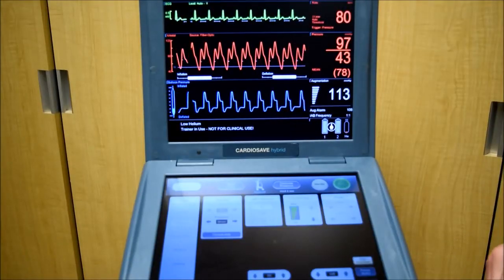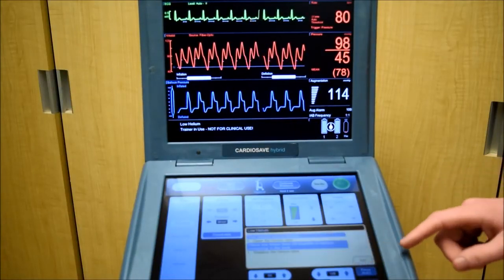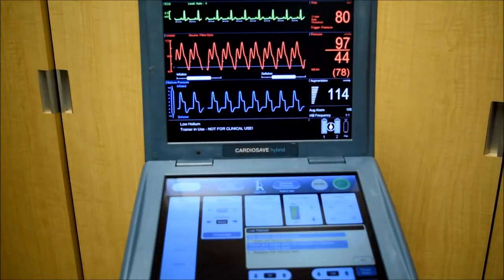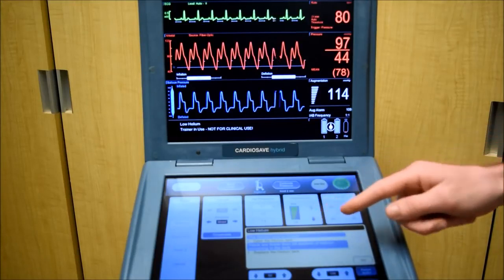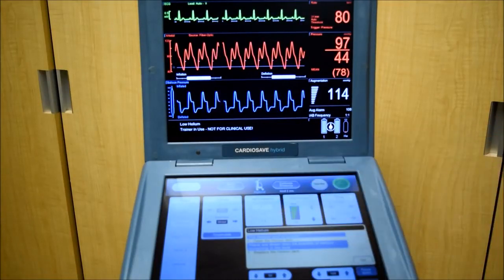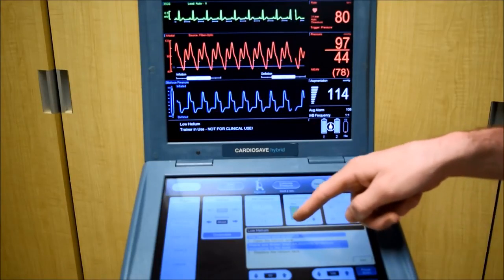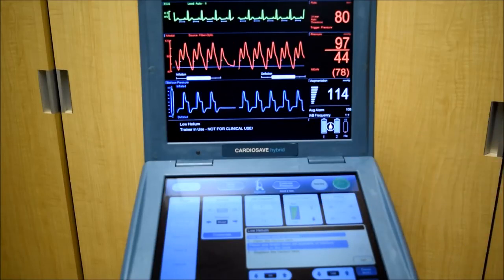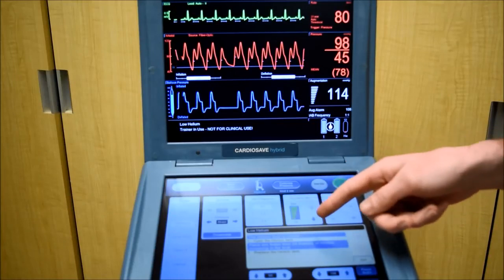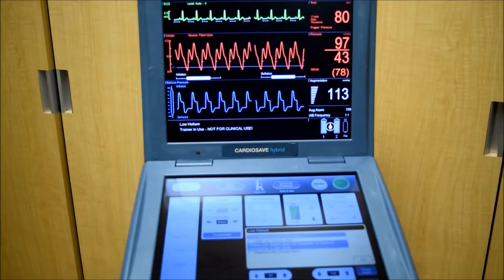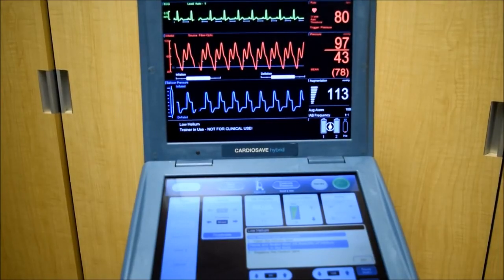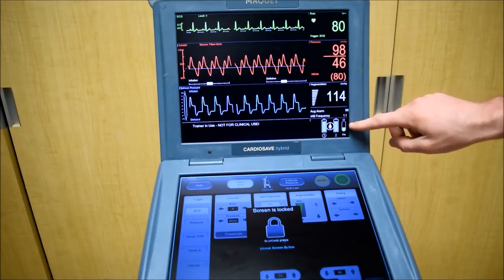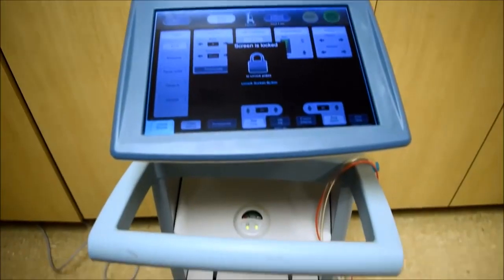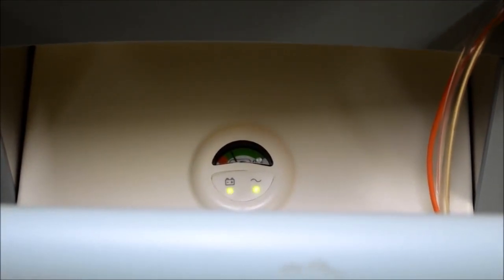To view any of the previous alarms, you can press Help Available. Alarms will both appear up here on the top monitor and also in the Help Below screen in the lower monitor. For example, right now we have a low helium alarm. The description here describes the alarm and how to fix it. With a low helium alarm, it suggests replacing the helium tank. You can check the helium tank level here, and you can also check it below the monitor here. Although this tank is still in the green, we can replace it anyways since it's low.